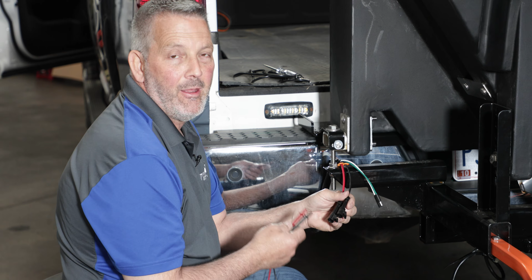Since we just tested the vibrator, we're going to test the red and black wire with our voltmeter. These are the wires that would go to the gear motor. We're going to see if we're getting power back here. This is another easy test to make sure we're getting power back here and the controller's feeding us what we need.